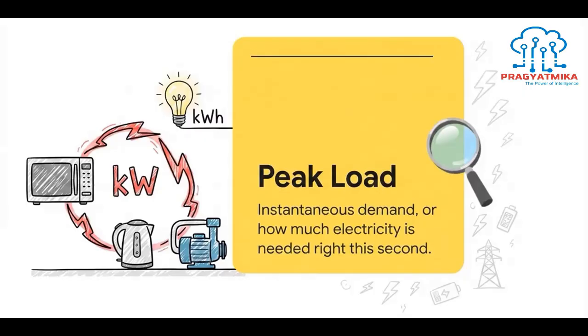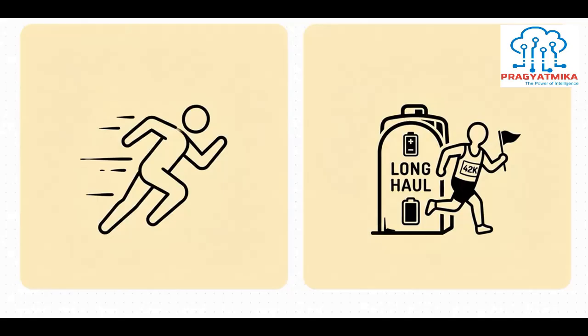Just think about walking into your kitchen. You turn on the microwave, a water pump, and click on an electric kettle all at the exact same moment. That massive instant pull, that's your peak load in kilowatts. But your average load in kilowatt hours, that's just the slow, steady burn of all your devices running over a full 24-hour period. It really boils down to the sprint versus marathon analogy. Your peak load sizes your inverter to handle the sprint, those massive short bursts of demand. But your average load, that sizes your battery bank for the marathon. They are two completely different metrics, doing two totally separate jobs.